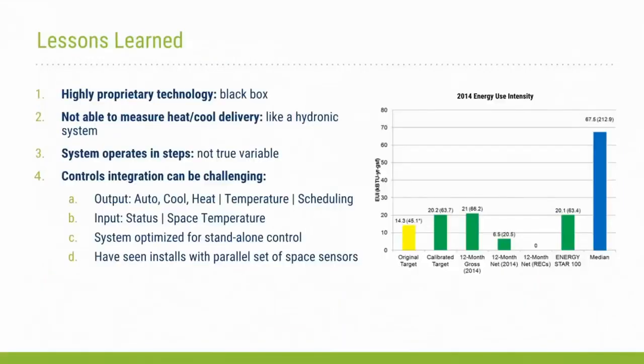So just some general initial observations. As has been mentioned, for every manufacturer, we are dealing with very proprietary technology, and so we are operating these in somewhat of a black box condition. So unlike a traditional air side or hydronic system where you can measure temperatures and flows and do an energy balance to see how it's performing in relation to electricity or natural gas input, that is actually much more difficult to do with a VRF system.